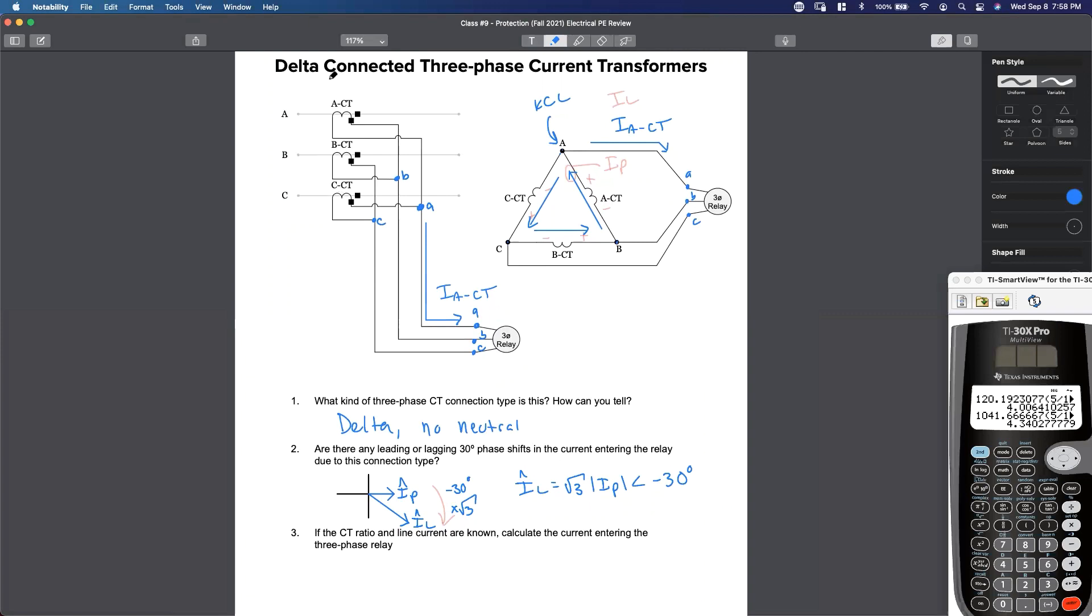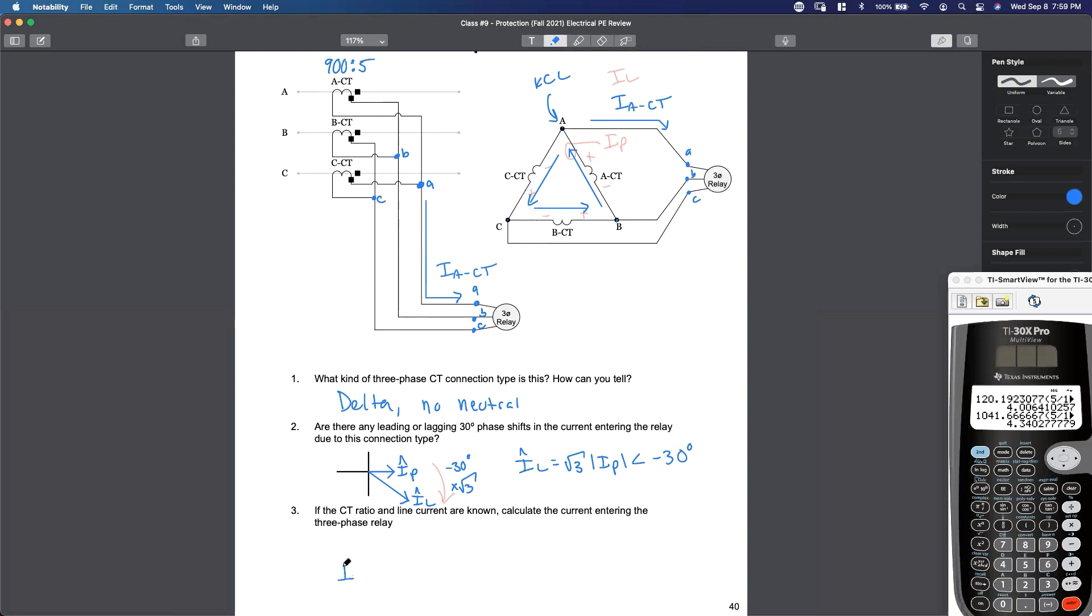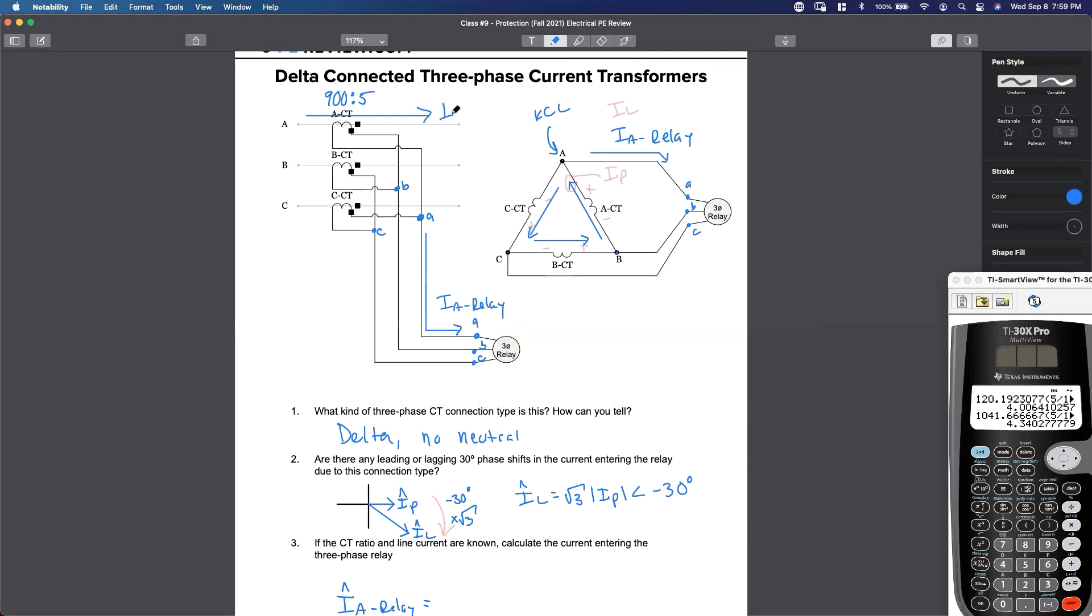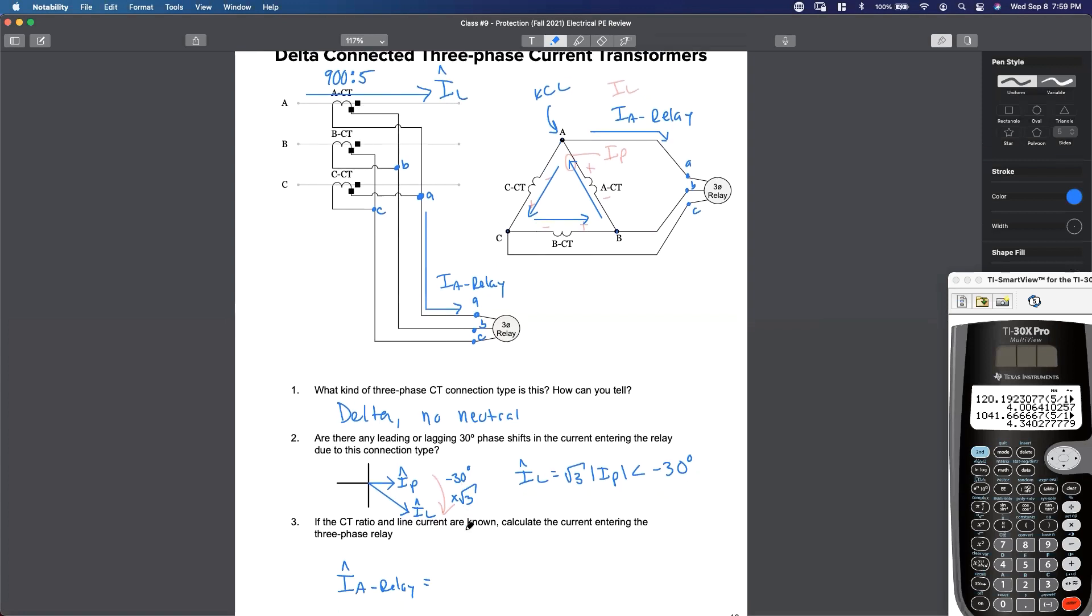Does that make sense? So let's assume what we did last time, 900 to 5. Assume that's our CT ratio. The CT ratio is known, and the line current is known. We'll just use magnitude I line. How do I calculate the actual current entering the A phase of the relay? What is complex IACT? Or in this case, really, actually, let's call this relay, IA relay, to differentiate between the current circling in the CT. How about that? What is IA relay?